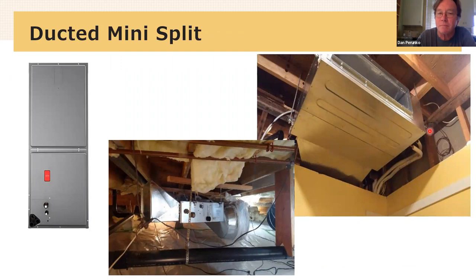Pardon me. These are ducted systems. This is a slim duct system, meaning it's a very small air handler. Heating and cooling capacities go from 7,000 BTUs per hour up to about 18,000 BTUs per hour. This is what's called a mid-static air handler, so same shape as this one, but bigger, right? Both taller and sort of thicker. And the capacities on these go from like a ton and a half, 18,000 BTUs per hour, up to 3 tons, 36,000 BTUs per hour.